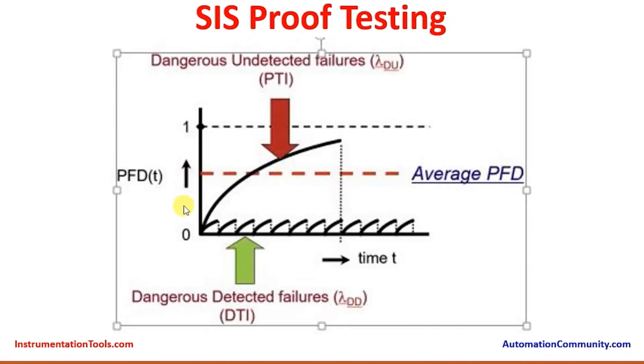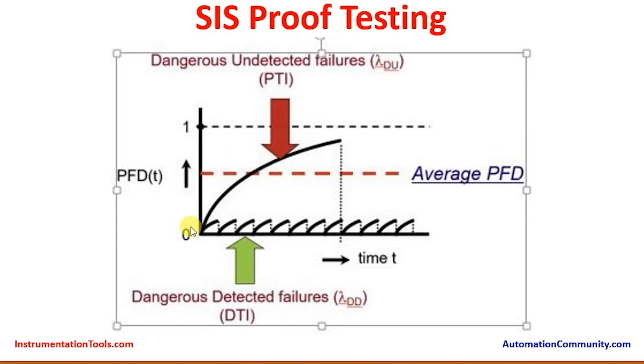Here we will go over a graph depicting how proof testing can improve system reliability. On the x-axis we have time running, and on the y-axis we have the probability of failure on demand. As time increases, the probability of failure on demand goes on increasing, so the possibility of dangerous failures increases. For each system there is an average PFD which is to be maintained, and if we fail to perform the proof test in time there is a chance of getting dangerous undetected failure. Whenever we do the proof testing as per the calculations and perform proper maintenance, the healthiness and reliability of the system is ensured.